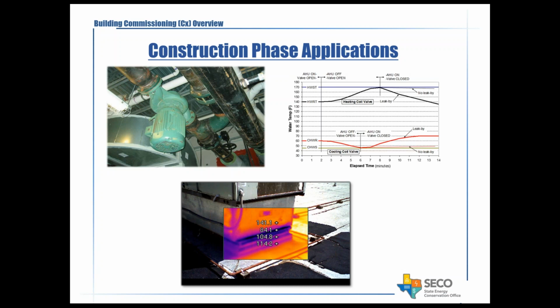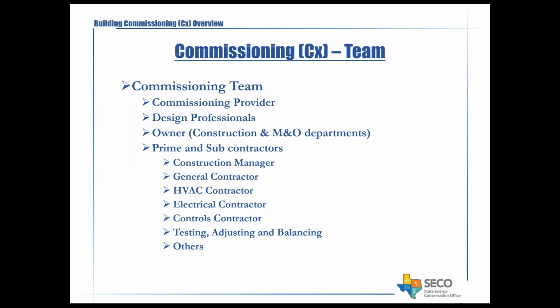Sometimes through the commissioning process, you will run into chill water valves or hot water valves that are leaking internally, and there's a specific kind of analysis done to identify those leaky valves, which results in more energy use. So those are the type of things that will happen in the commissioning process that become very useful. These are just a few examples.